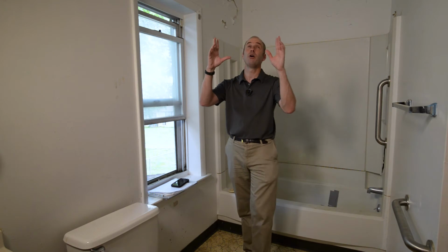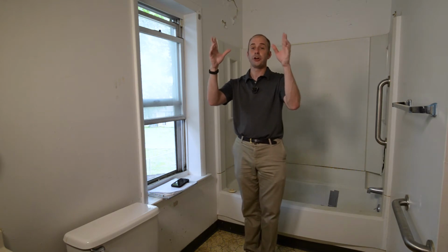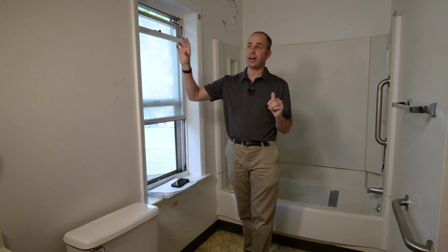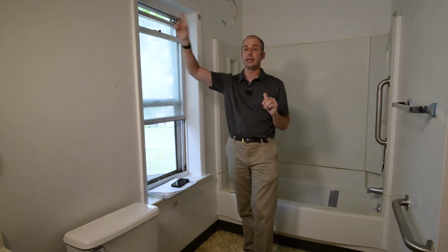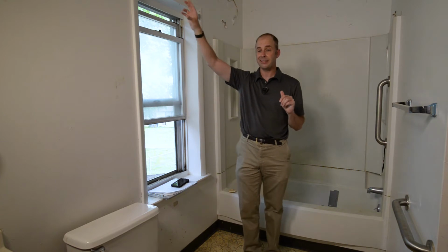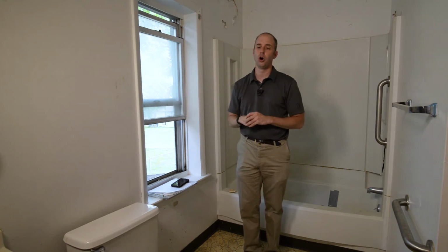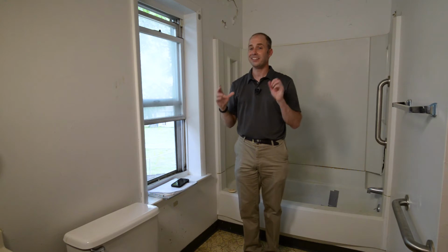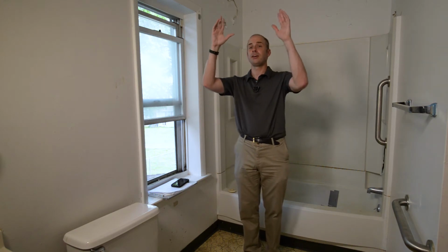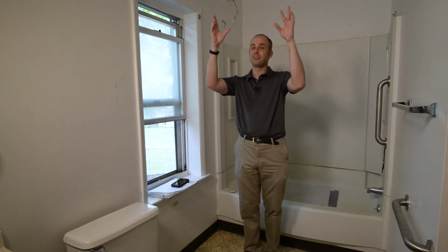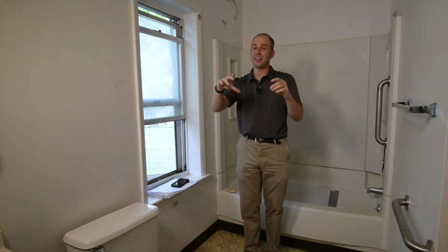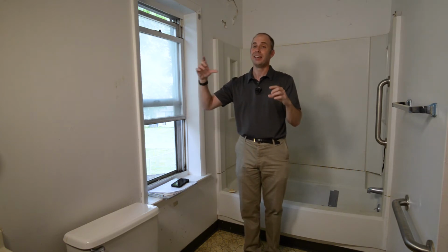Now, with the fan itself, we need to make sure that it's secured and properly installed, and that any wiring going to it is actually protected. At times it will be done through conduit, and we need to make sure that it's actually in the conduit and not just wire tacked to the wall. Also, the fan needs to vent to the exterior. This is a common item that we come across, where you can see the fan in here that just goes through the ceiling, but when we get up to the attic areas, we will see that the fan does not terminate to the outside, and it actually just dumps the air into the attic.